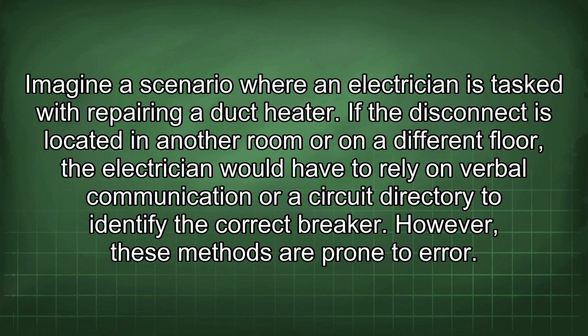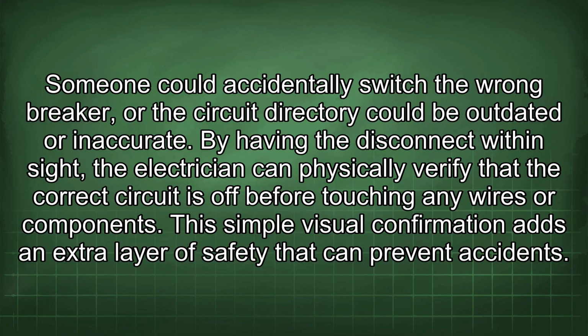Imagine a scenario where an electrician is tasked with repairing a duct heater. If the disconnect is located in another room or on a different floor, the electrician would have to rely on verbal communication or a circuit directory to identify the correct breaker. However, these methods are prone to error. Someone could accidentally switch the wrong breaker, or the circuit directory could be outdated or inaccurate. By having the disconnect within sight, the electrician can physically verify that the correct circuit is off before touching any wires or components. This simple visual confirmation adds an extra layer of safety that can prevent accidents.